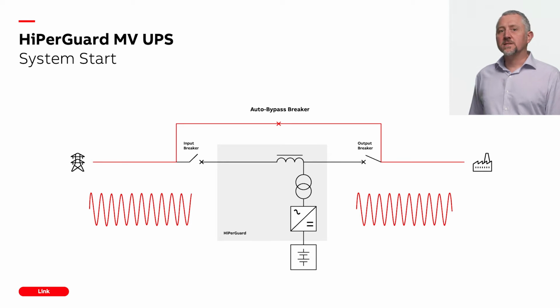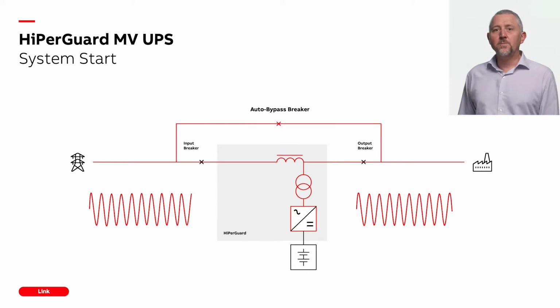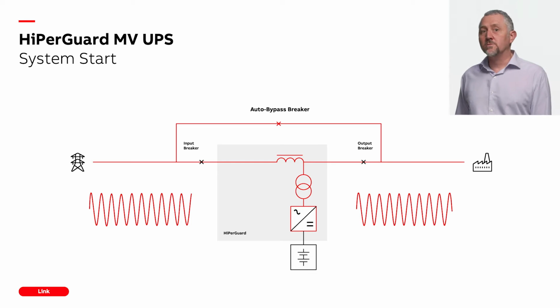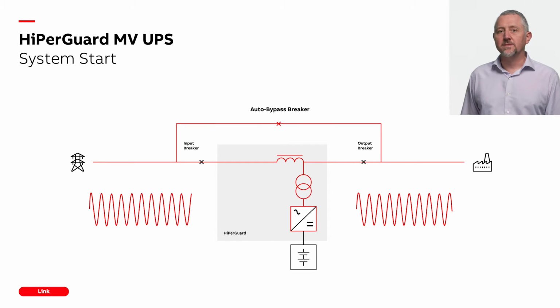Let's walk through the HiPerGuard startup process. Operation of the MV switchgear is controlled by the HiPerGuard's Graphical Display Module, GDM, and system controller. With a simple command, the auto bypass breaker closes, allowing power to flow from the grid to the load. The HiPerGuard then starts the synchronization process, aligning its output voltage in phase with the grid, while keeping the load powered by the grid. Once in sync, the input breaker closes with the load still powered through the auto bypass breaker as the low impedance path.